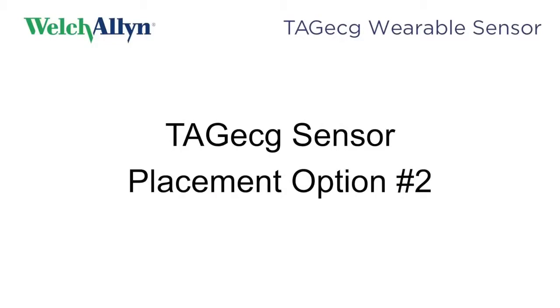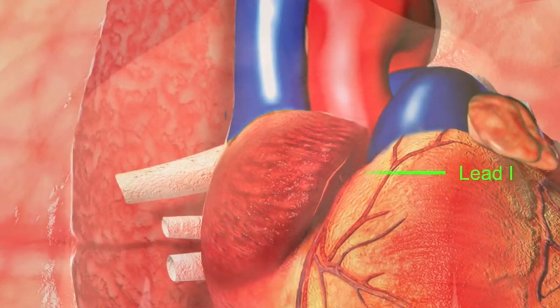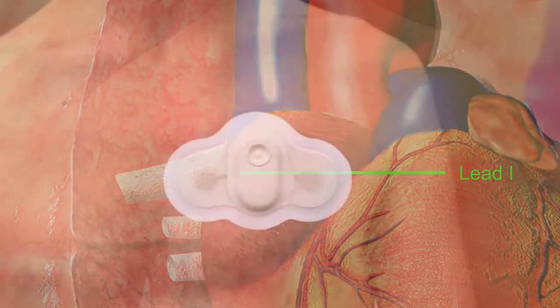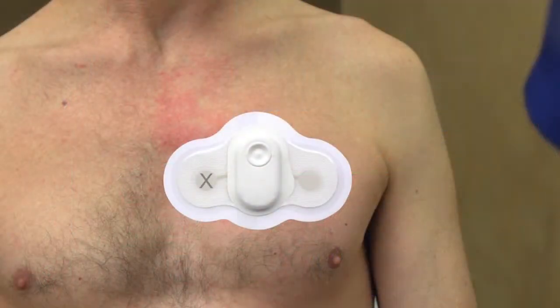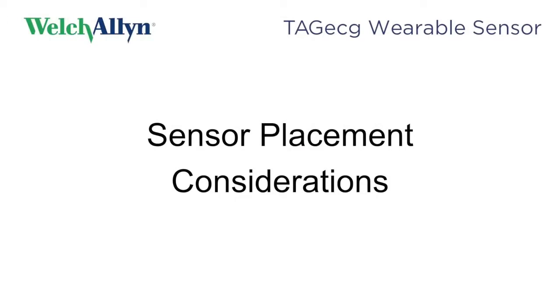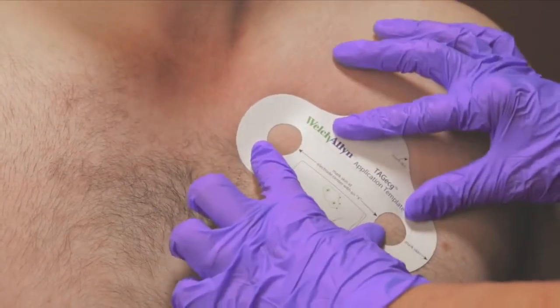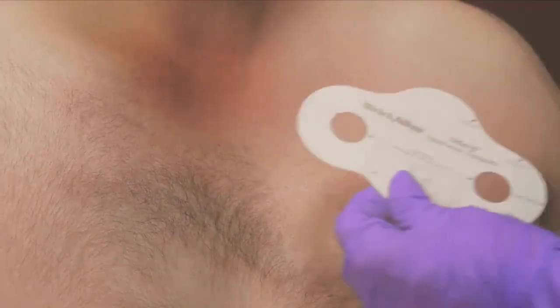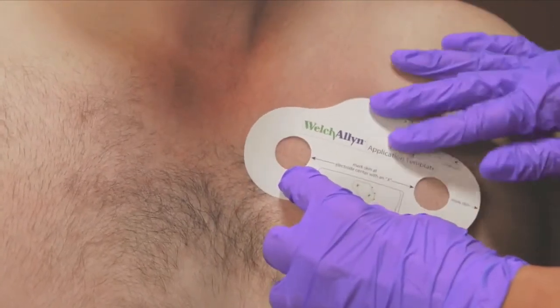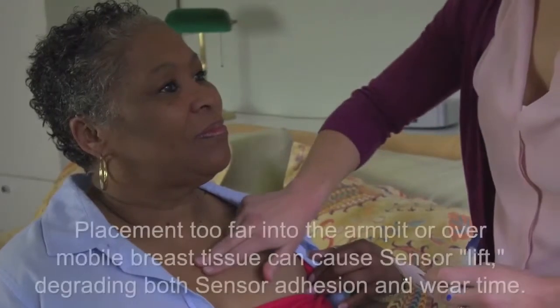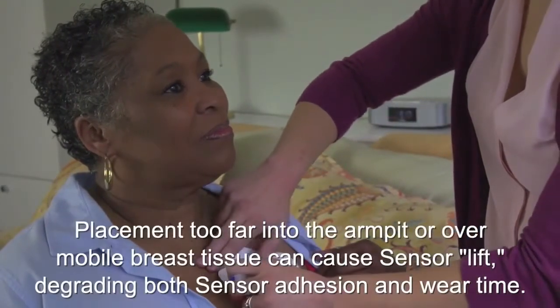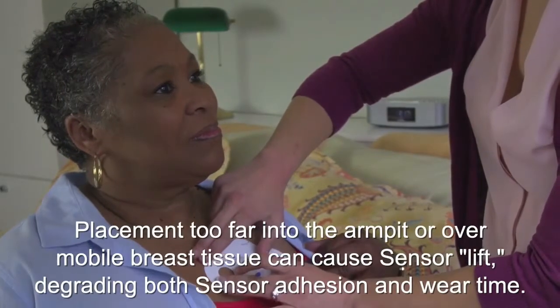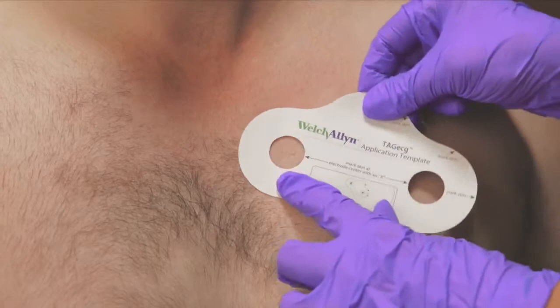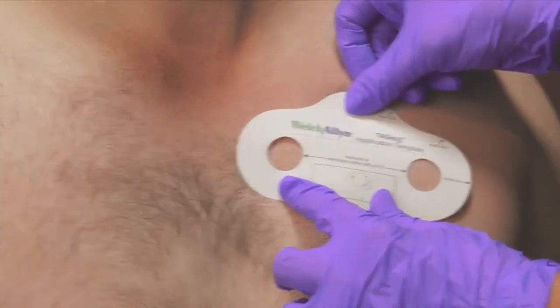Placement option 2 is aligned with lead 1 of a standard 12-lead ECG. For option 2, place the sensor horizontally at the third or fourth intercostal space, with the right gray electrode placed proximal to the patient's sternum. TAGecg sensor placement considerations. Avoid locating the sensor over the patient's left breast tissue or into the patient's left armpit. If needed, place the sensor closer in towards the patient's sternum and slightly higher. Placement too far into the armpit or over mobile breast tissue can cause sensor lift, degrading both sensor adhesion and wear time. This video demonstrates how to place the TAGecg sensor in the option 1 diagonal position.